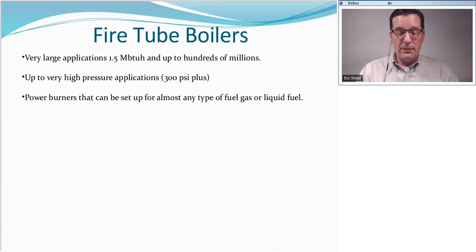So my bottom line is, if you are accidentally called out to a high pressure application, you walk in the boiler room, walk yourself right back out again. There's a whole other series of certifications, stationary engineer licenses, and boiler operators licenses that are necessary to work on those systems. So just be aware of that. Pay attention to what your pressure is before you get in over your head.